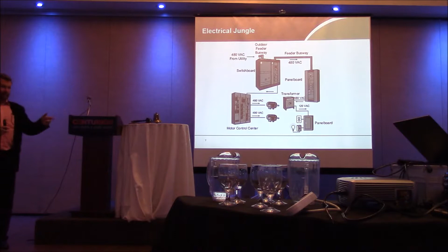The nice mechanical guy gave me my loads. My loads came out to around 275 amps. He suggested a 300 amp motor control center. I wasn't feeling trusting, and I put in a 600 amp motor control center, because remember, I'm talking about a facility that shut this switchboard down once every 2 years. So when the time came to actually implement it, I think the motor load came out overall to about 540 amps.